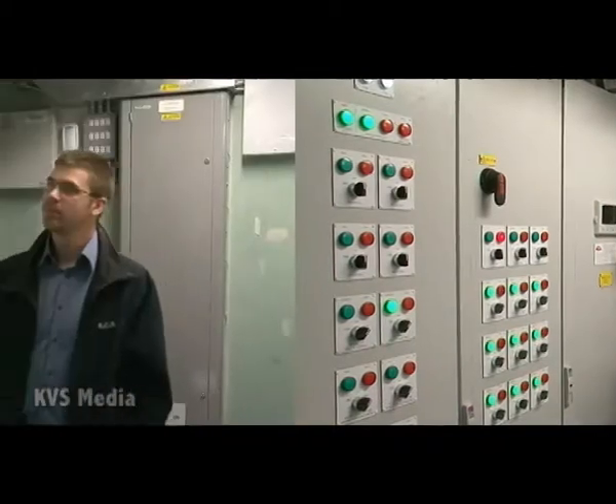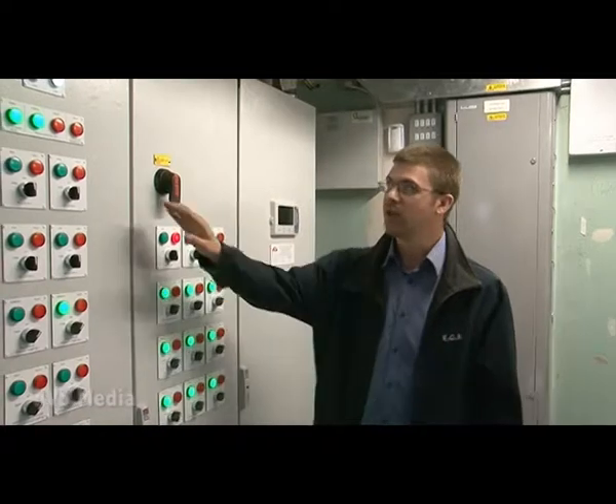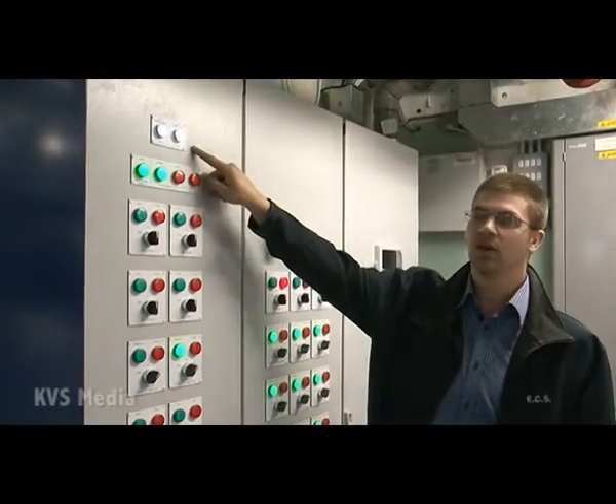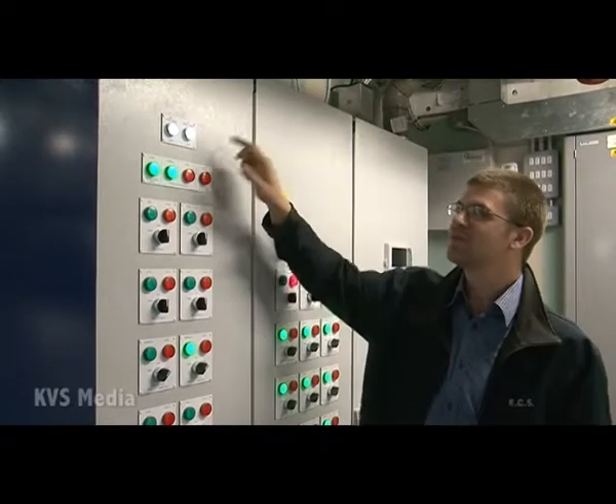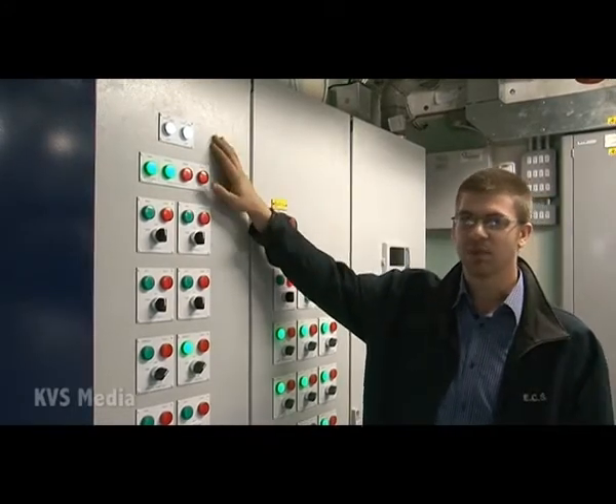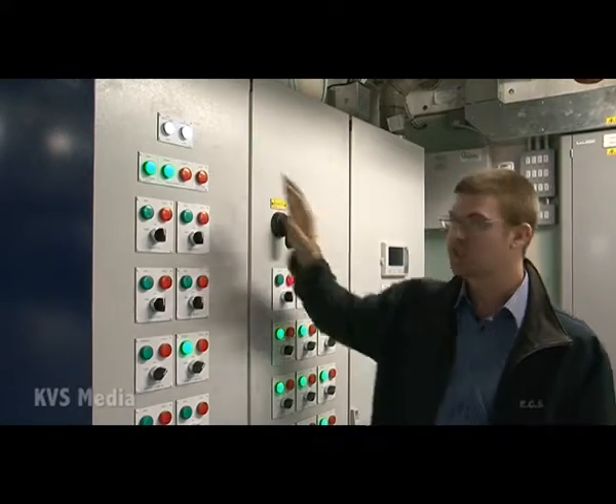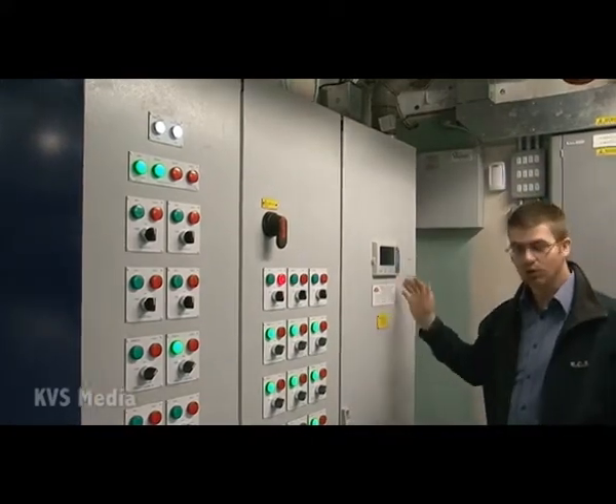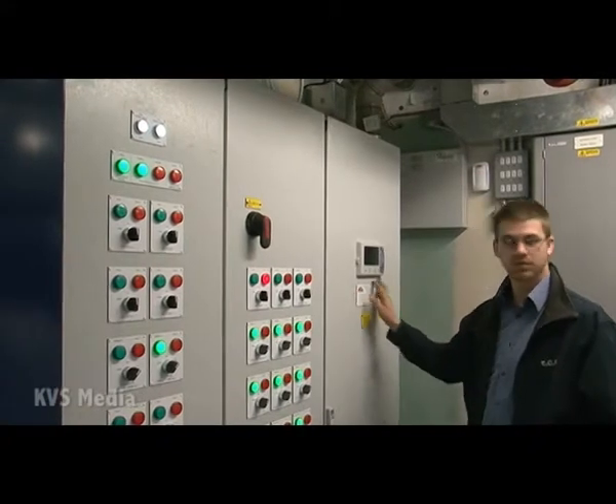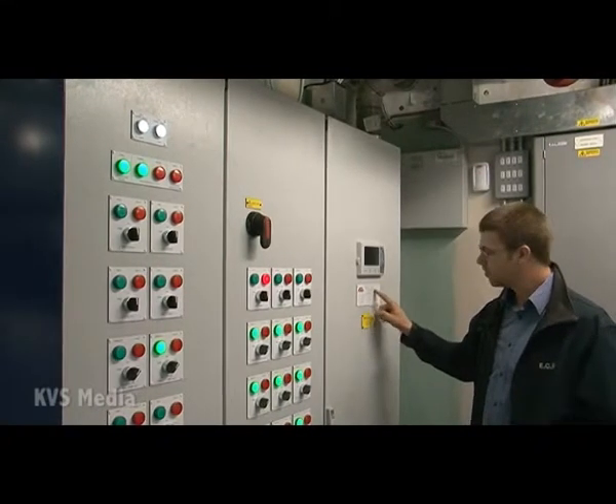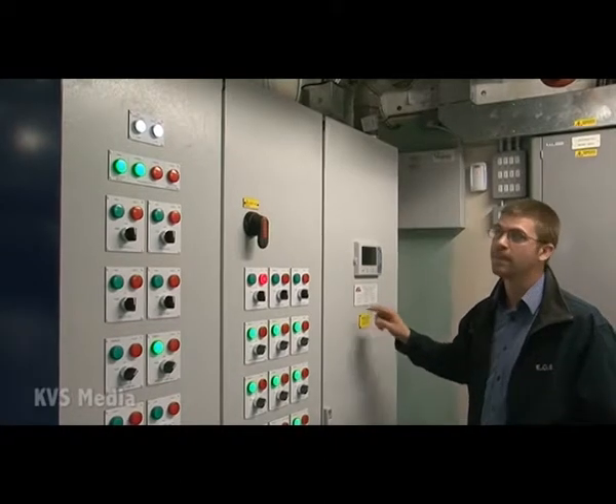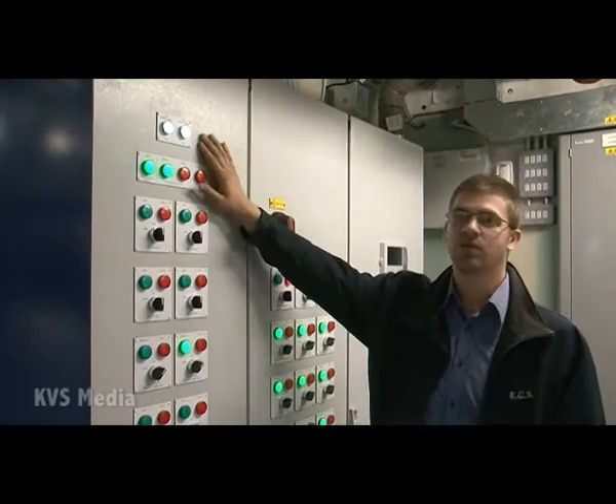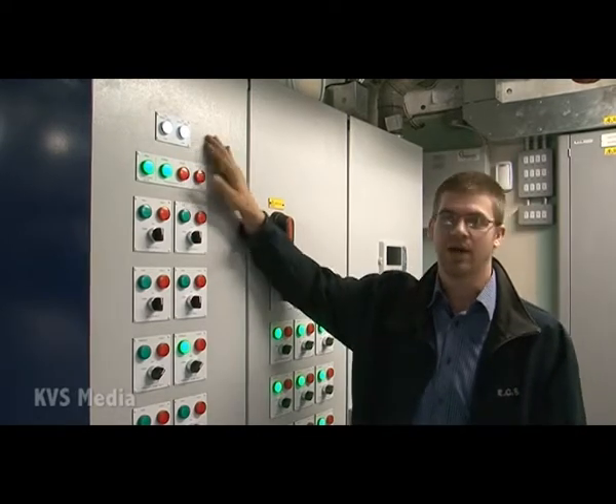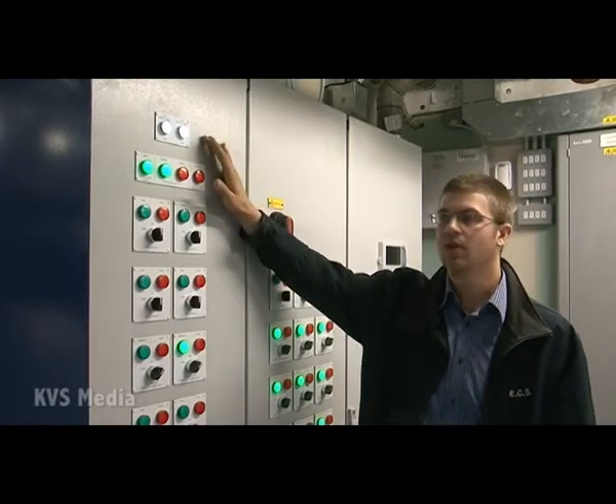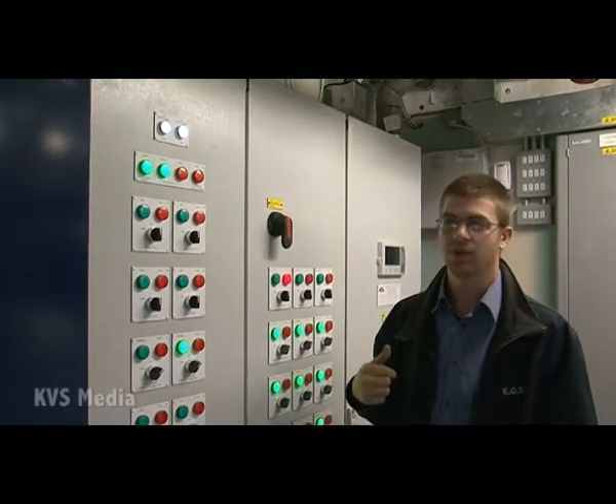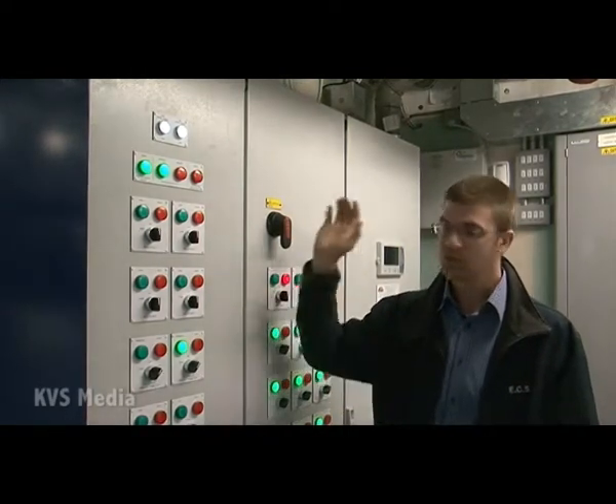points of the system. With regard to the fascia of the control panel, up the top here we've got two white lights. It's fairly simple. If they ever go out, there's a fairly serious problem, and it's best to call the number, call your maintenance providers, or by all means call us. The number's on the front of the door, and the job reference is on here as well. So those white lights indicate that the control circuit is on, live and healthy. They will only go out in a serious failure, power cuts, or if a fire alarm has gone off. There's a knock-off button by the door which will shut all of this down.